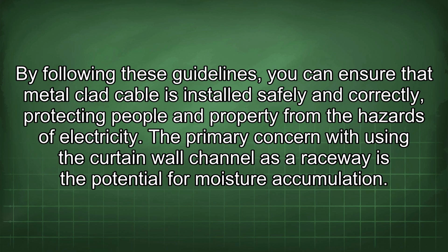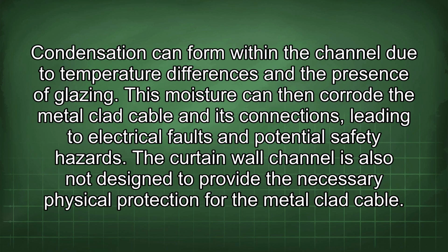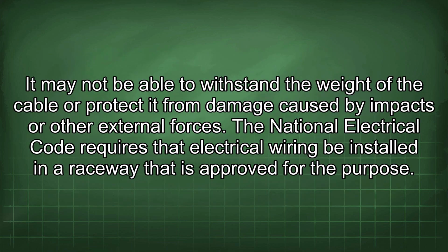The primary concern with using the curtain wall channel as a raceway is the potential for moisture accumulation. Condensation can form within the channel due to temperature differences and the presence of glazing. This moisture can then corrode the metal-clad cable and its connections, leading to electrical faults and potential safety hazards. The curtain wall channel is also not designed to provide the necessary physical protection for the metal-clad cable. It may not be able to withstand the weight of the cable or protect it from damage caused by impacts or other external forces.